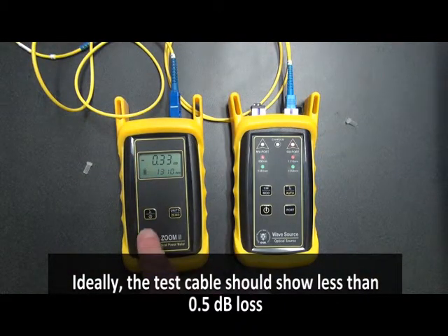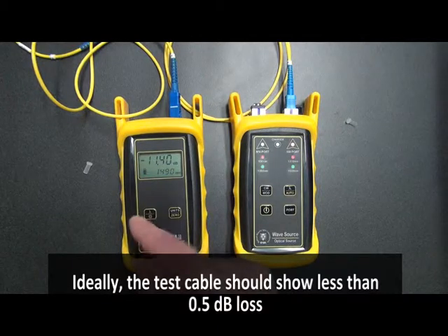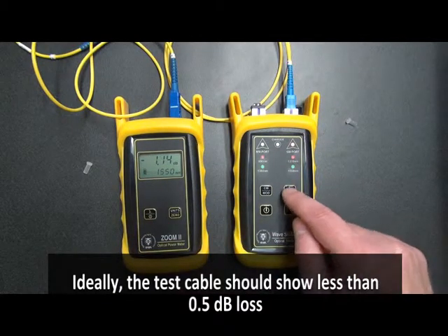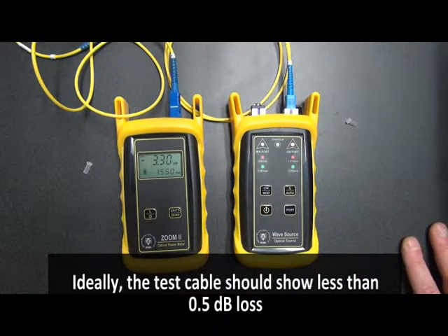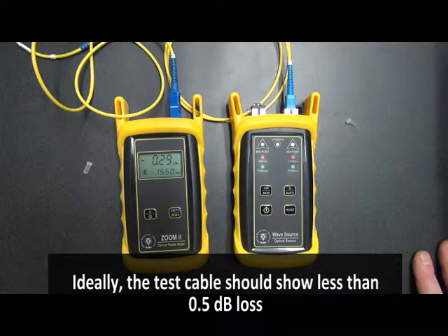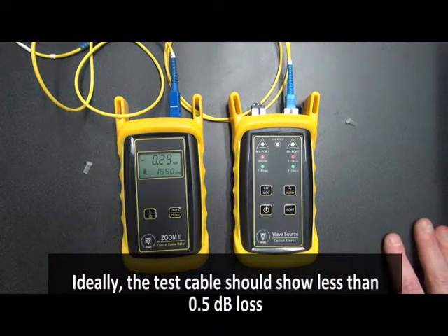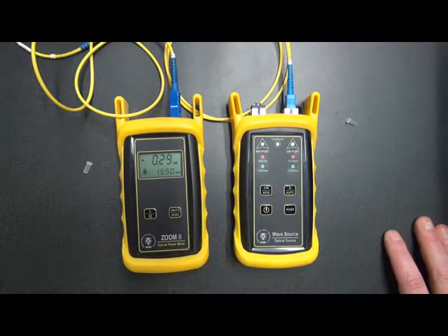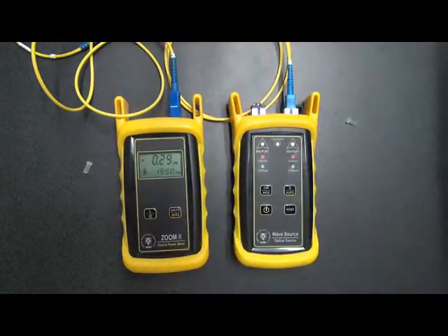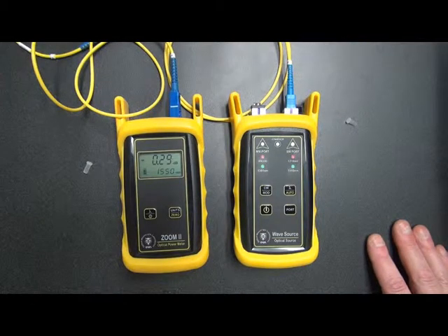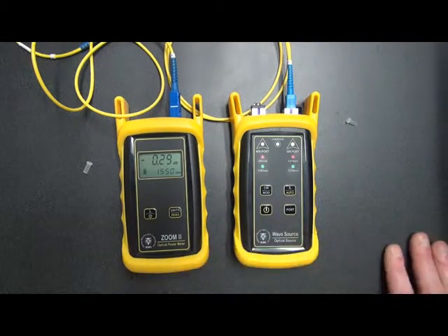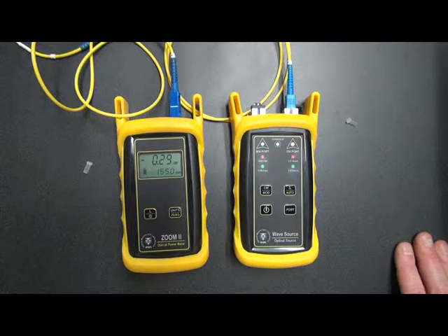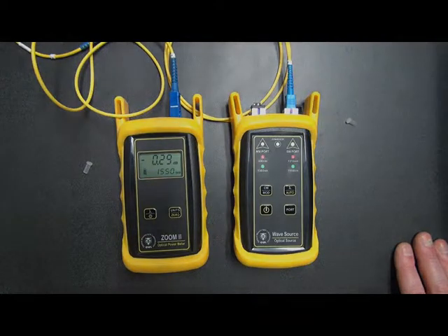If we want to check at 1550, we simply, again, press the wavelength button on both units to switch to 1550, and we see we have a reading of around 0.3. Again, it's about the same as before. So we know that both of these patch cables are okay to use, and that the equipment is reading at its calibration levels, so we're ready to continue with our test.